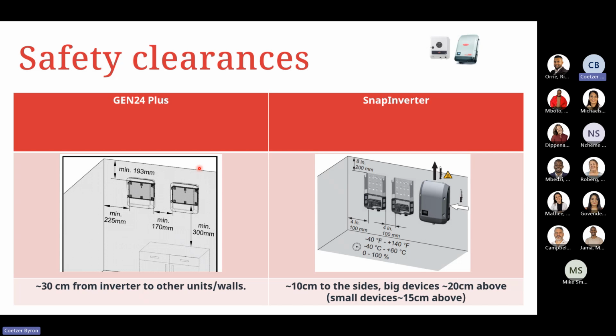Your safety clearances, so your distance between the inverters. Always with the SNAP inverters, we recommend 100 millimeters between the units. So it's 10 centimeters from side to side on the big devices and 20 centimeters above the units, as well as 15 centimeters above for the smaller units. This is just to aid with installing the units as well as to prevent heat soak, because what happens is the fans draw cold air from the sides and push it out through the top of the heatsink. So if there's a roof that is too low, for example, we would then be recycling that hot air through the unit and through the heatsink, and we'll eventually get an error code for excessive temperature on the unit itself.